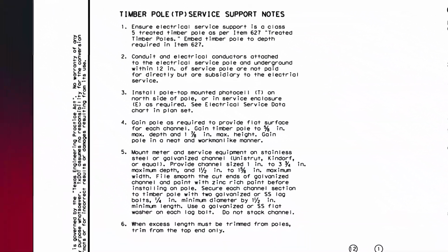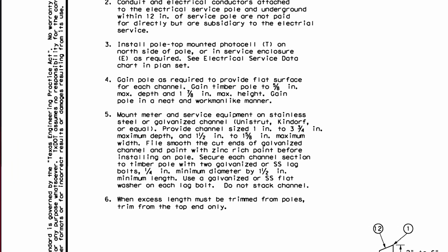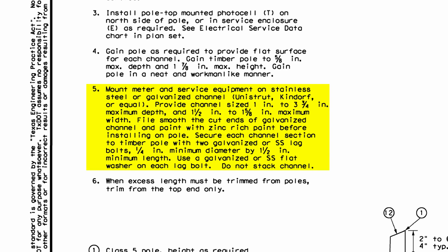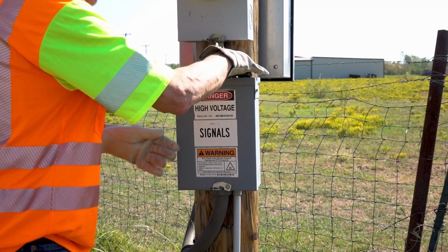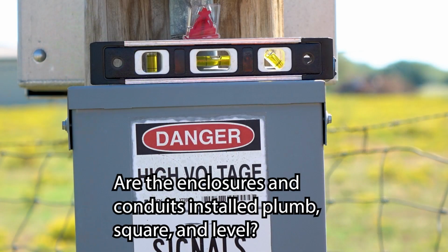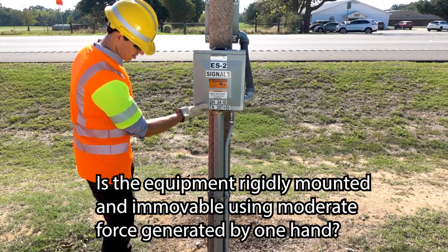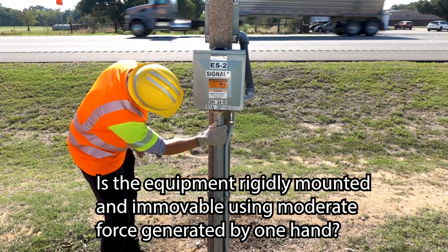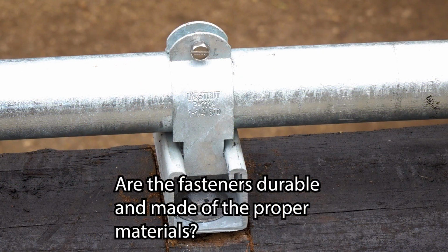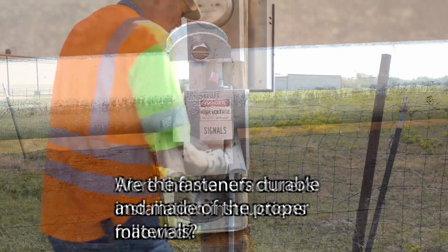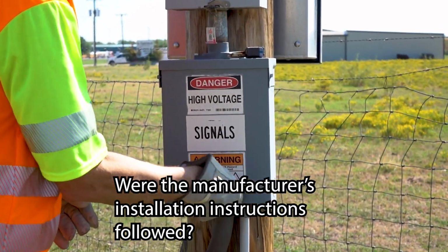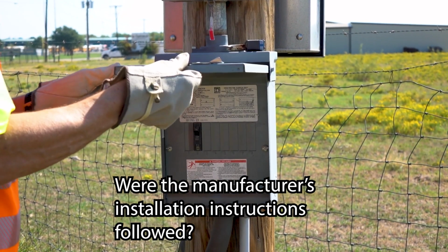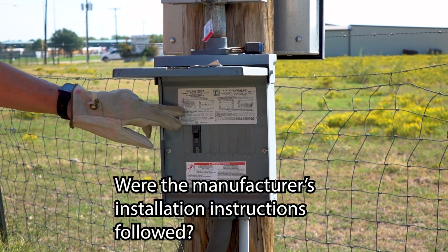Instructions for mounting electrical enclosures on a timber pole are on ED 10. Material requirements and mounting methods are specified in the notes. The inspector should inspect the mounting of a Type T service enclosure and meter base using these guidelines. Are the enclosures and conduits installed plumb, square, and level? Is the equipment rigidly mounted and immovable using moderate force generated by one hand? Are the fasteners durable and made of the proper materials? Were the manufacturer's installation instructions followed? The answers to these questions will indicate how well the contractor has complied with the specifications and plans.